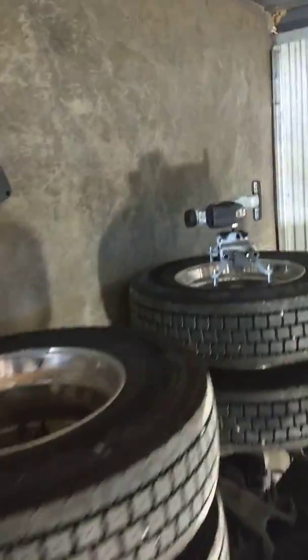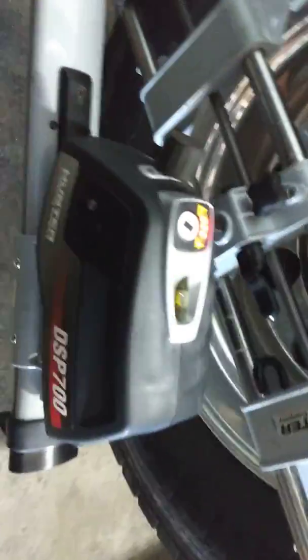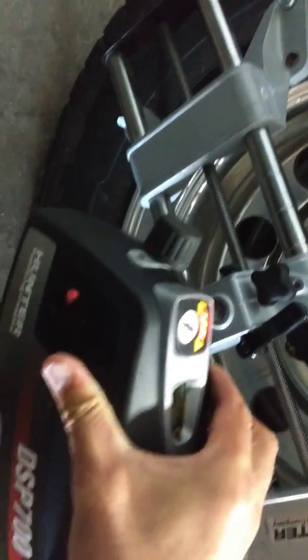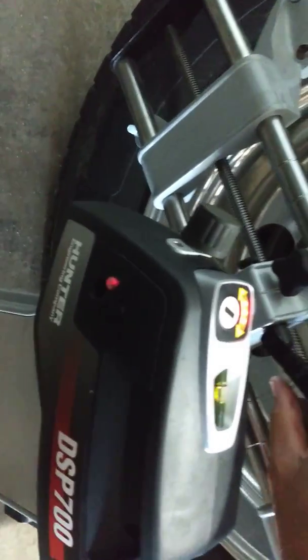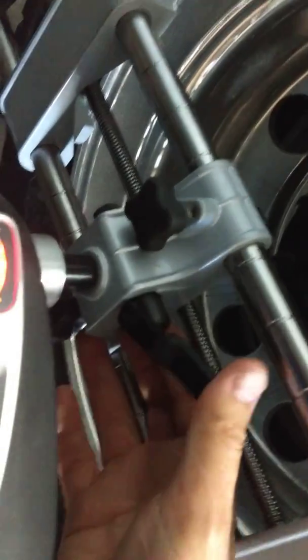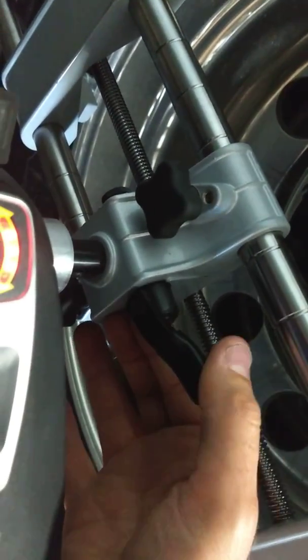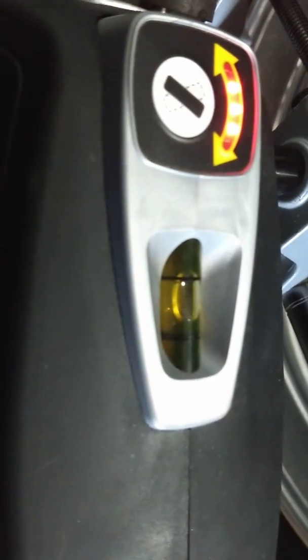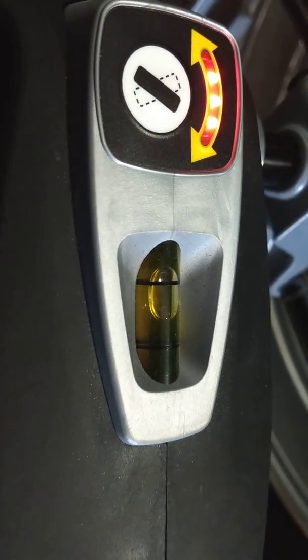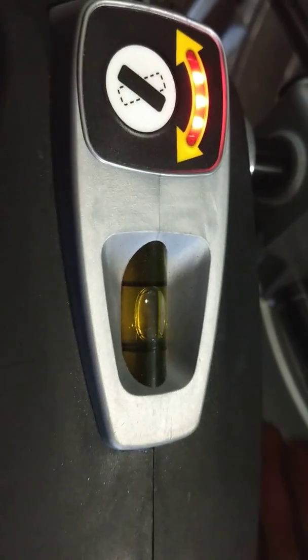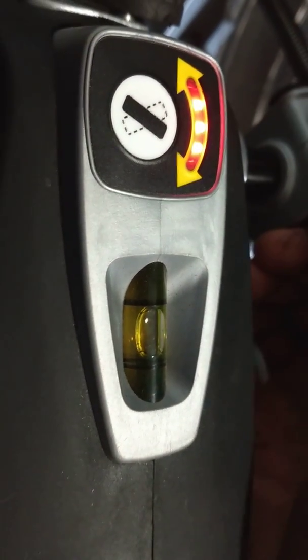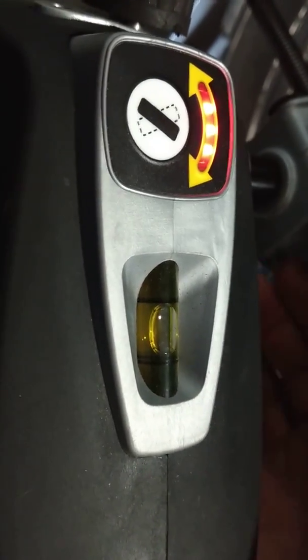So we walk it back over here. We disengage the right rear, set it off to the side temporarily, carefully. We re-engage the front sensor from the left front to the right rear. Now, we're going to level it with this butterfly. So we put just a little bit of pressure on this, and then we look at our level bubble, and we start leveling, and then we tighten this down, and it just needs to be perfectly level for this. That's the only room for human error in this process.